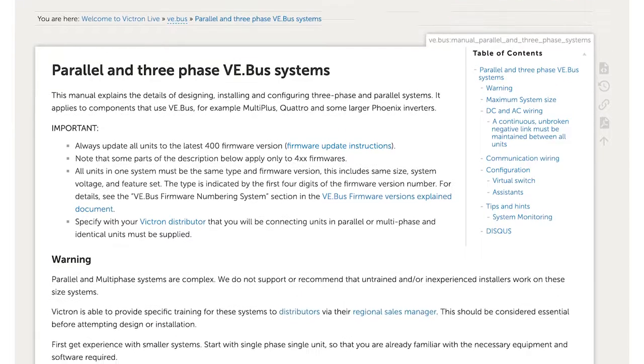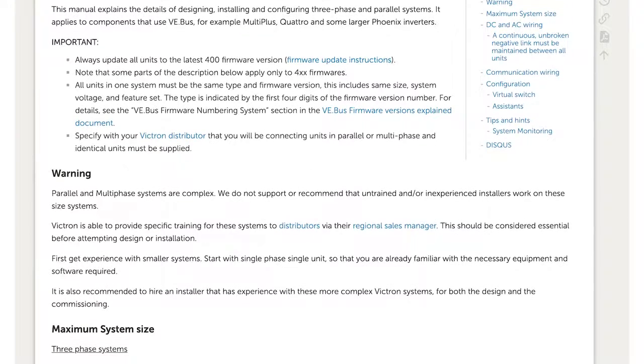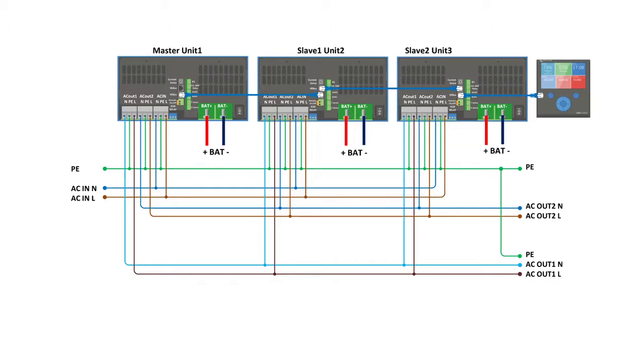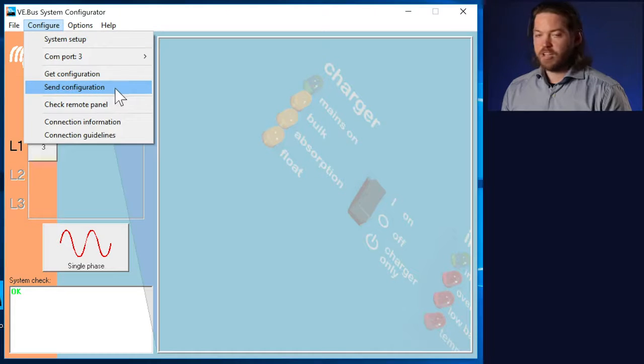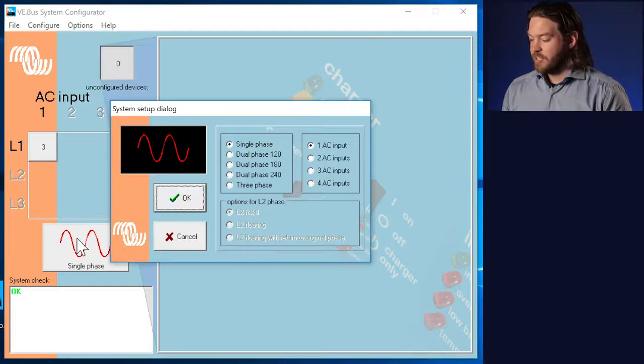There's other things to consider in parallel system design, and you should cover these off in the manual. The most specific is on the AC output. There needs to be equal resistance on the AC output as well. This is the AC wiring diagram for a parallel configuration. Remember, you can add 3 phase and parallel systems together to build very large systems. I'm now going to convert these systems back to 3 phase.